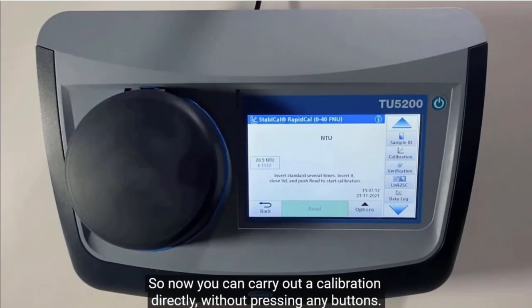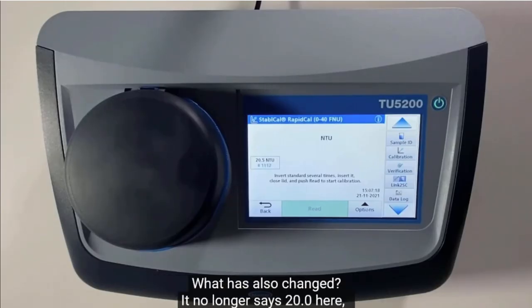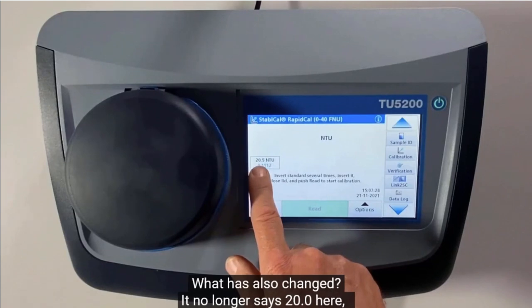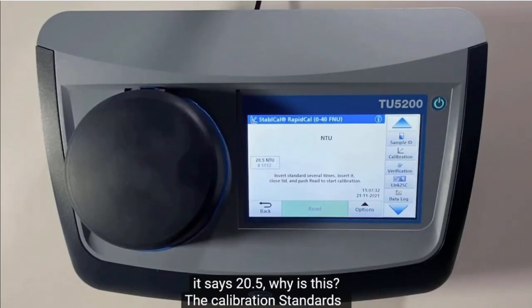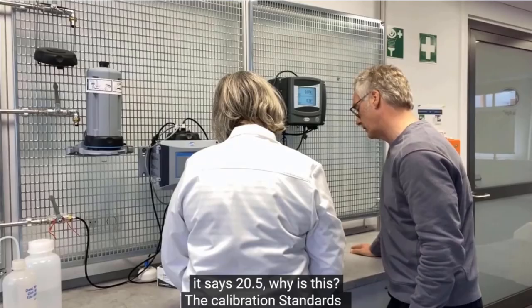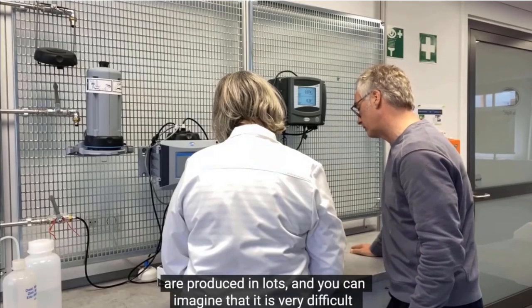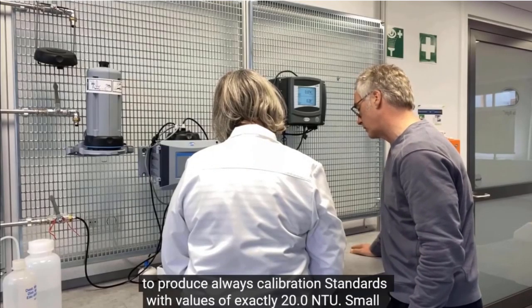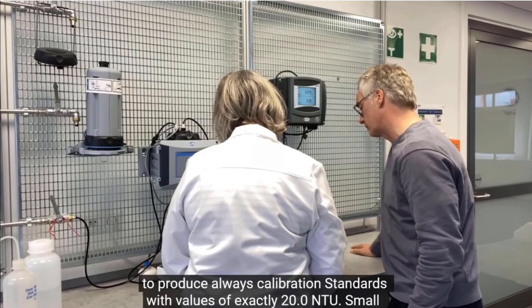So now you can carry out a calibration directly without pressing any buttons. What has also changed? It no longer says 20.0 here, it says 20.5. Why is this? Calibration standards are produced in lots, and you can imagine that it is very difficult to always produce calibration standards with values of exactly 20.0 NTU.